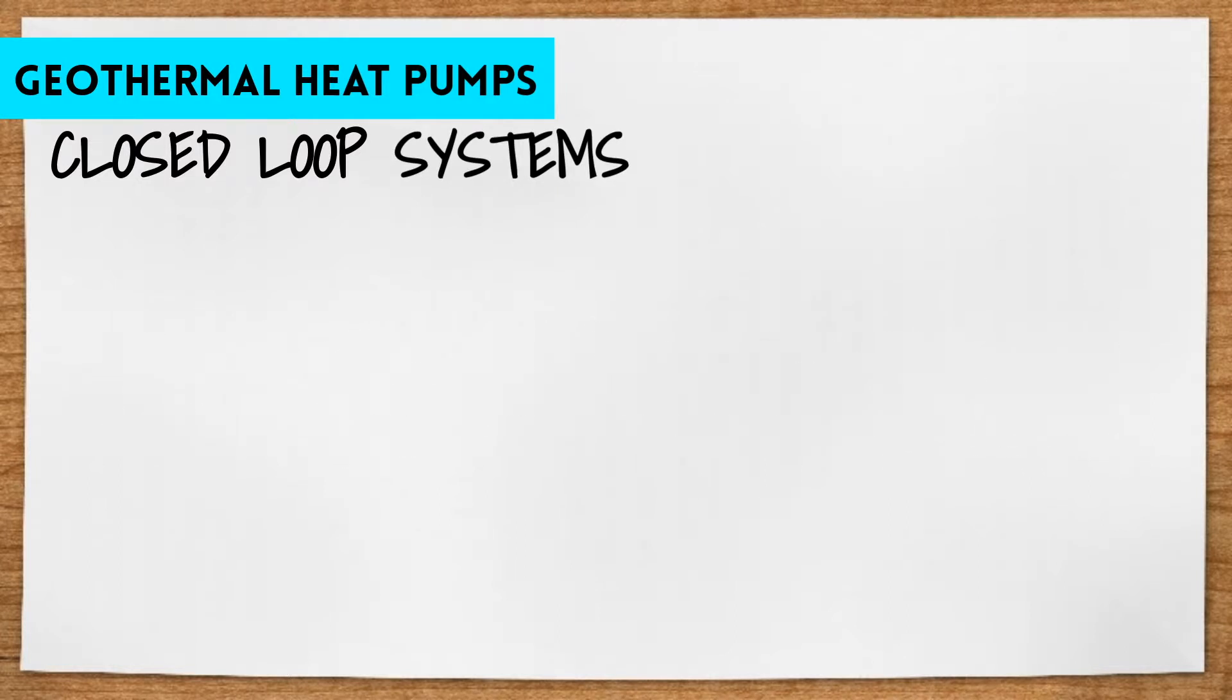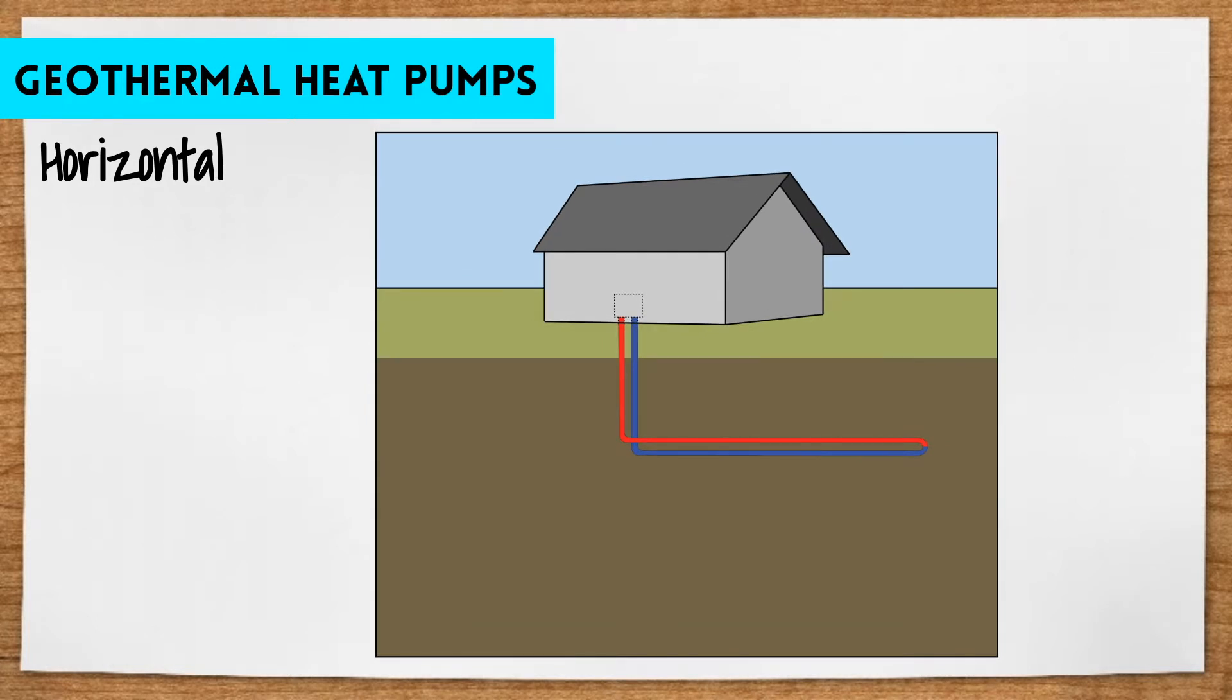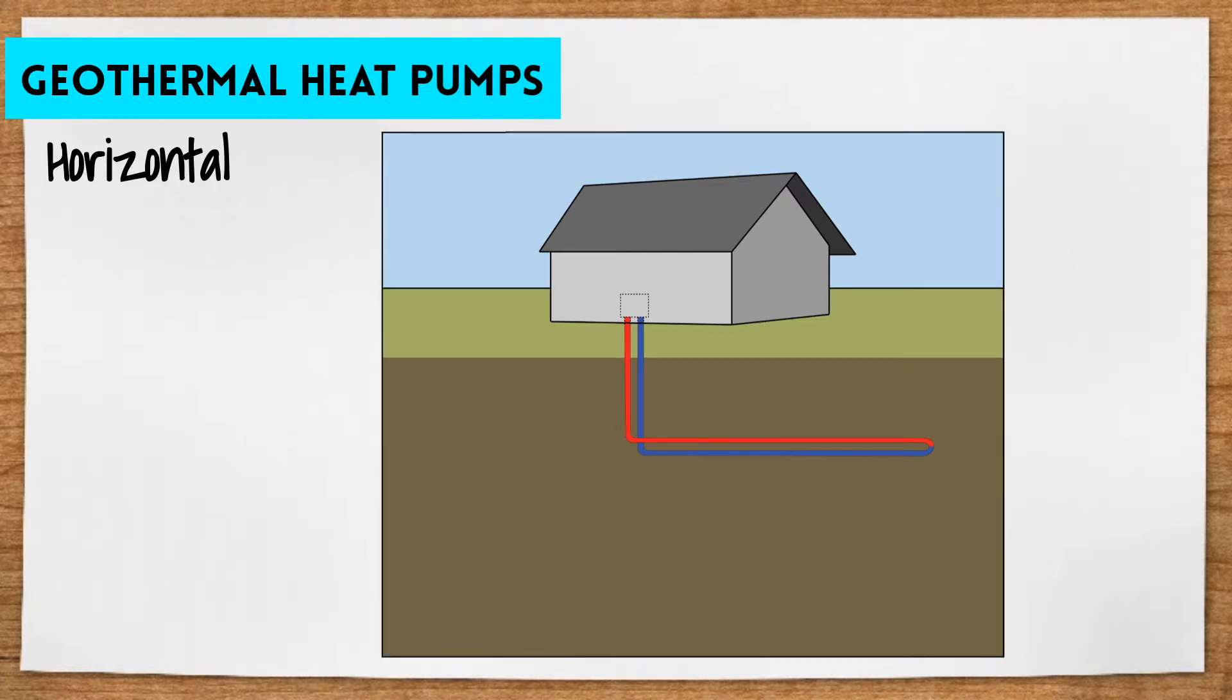The three types here are horizontal, vertical, and pond or lake configurations. So, the first one, horizontal, is most often seen in new construction residential projects that have a sufficient amount of land available to run the piping. This configuration requires trenches between three and six feet deep.